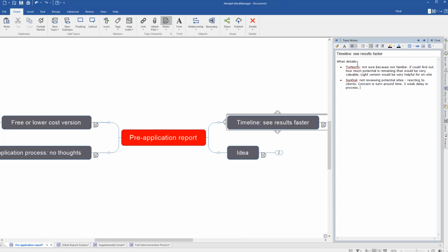So right off the bat, I'm going to rely more on the interconnection queue and available information rather than risk multiple applications getting ahead of me and creating DG on that feeder or substation that will put me into sequential review. And that turns out to be a very long wait. So sequential review on top of 3 weeks, client getting 5, 6 to 10 weeks delays to get this information. It's a non-starter in many ways, and that's why we haven't been using it.